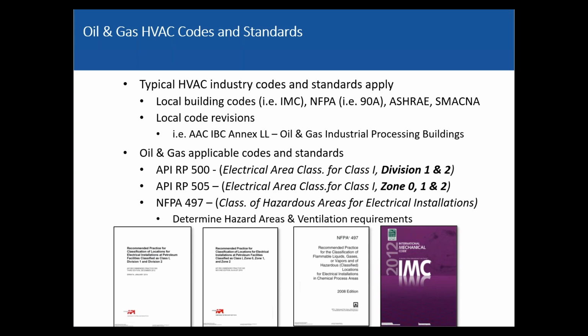They're electrical area classification. The difference being Div 1 and 2, Zone 0, 1 and 2. Div 1 and 2, as it's referred to, that's mostly in the US. You can kind of broadly say that. And then Zone, 505, it's a little more European in application. But you can use either place, and that would be during the code setting phase of your project, where they would identify that. And then NFPA has to get in on the game, and they have 497, which is their classification of areas for electrical installations. And that's basically talking about, if we have a hazard process, well, I got a good example here. I'll come back to that.